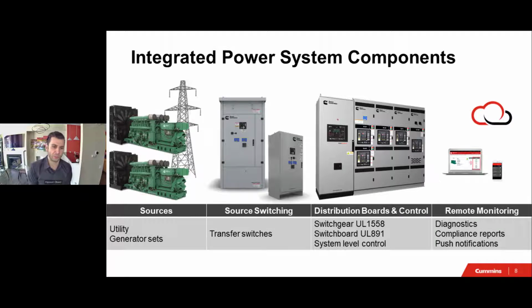And the distribution board, the term that you most commonly use is switchgear. And technically switchgear falls under UL 1558, and is typically designed in a lot of circumstances to handle up to 30 cycles of short time rating. And then there's a switchboard, UL 891, and like I said, in some applications, you'll have a system level controller.